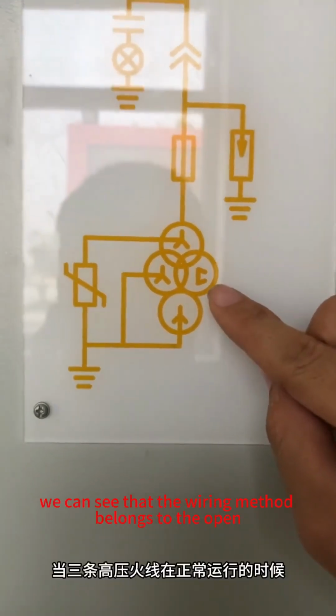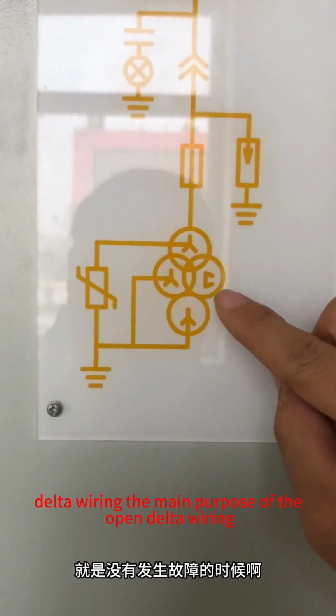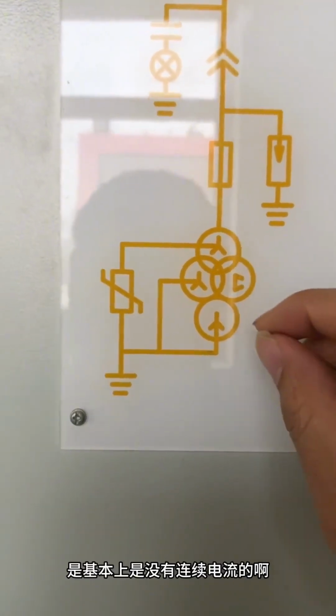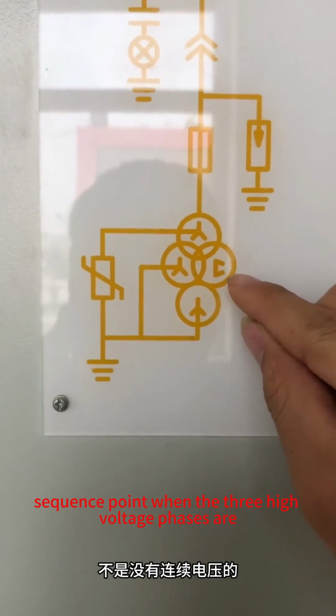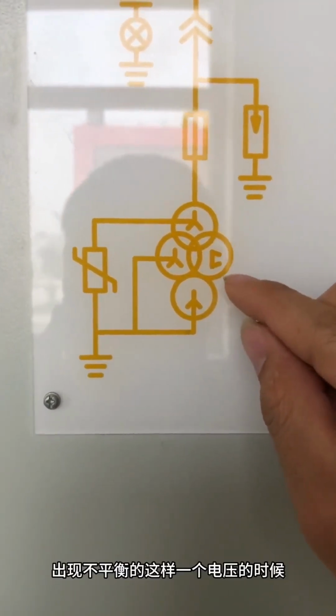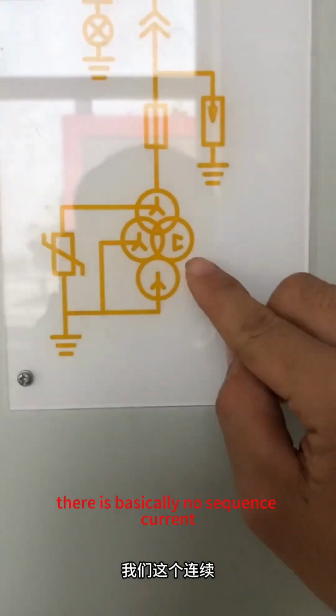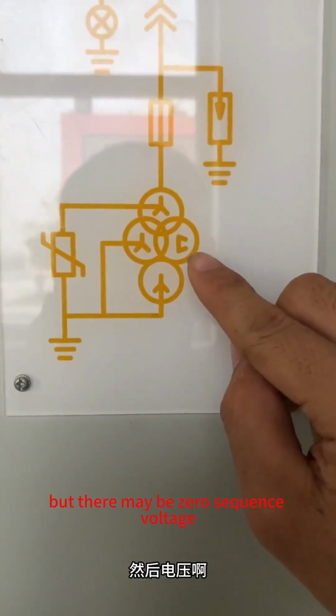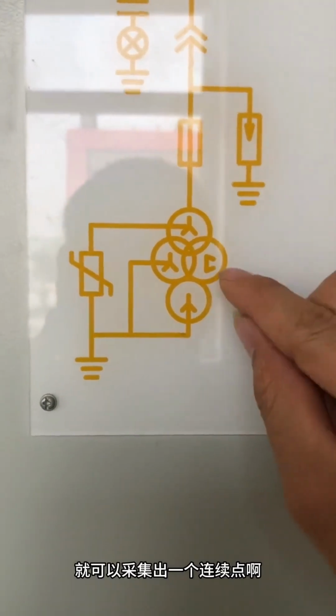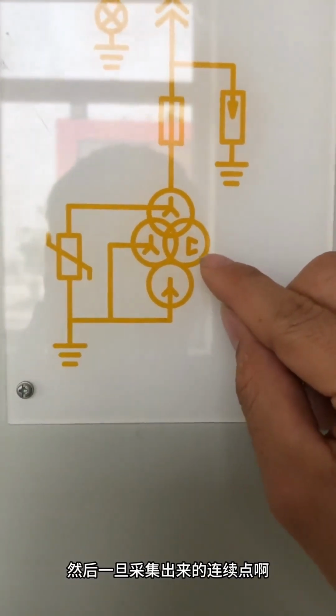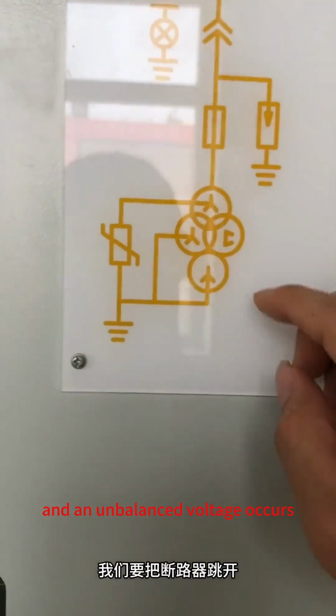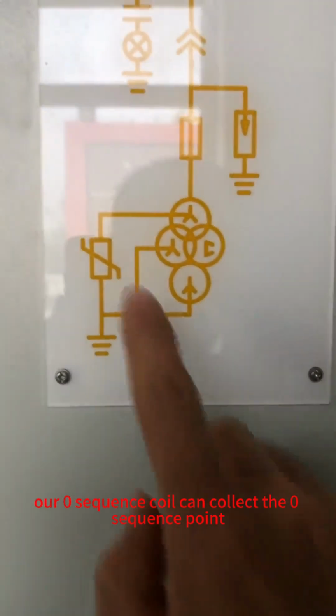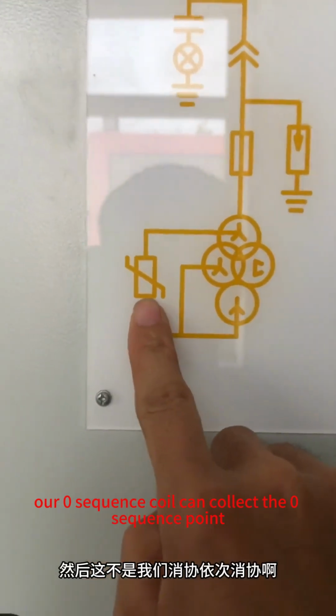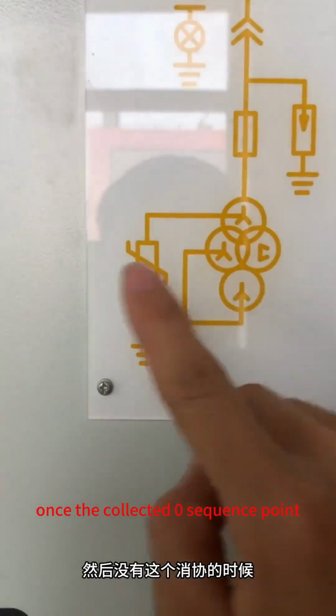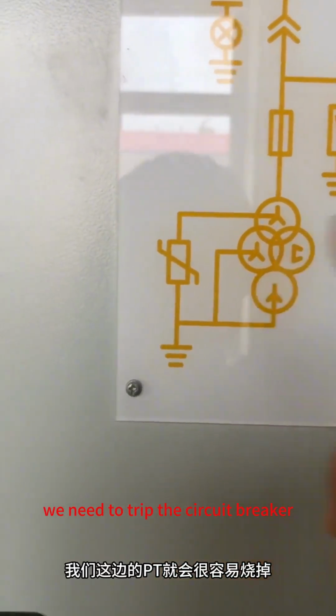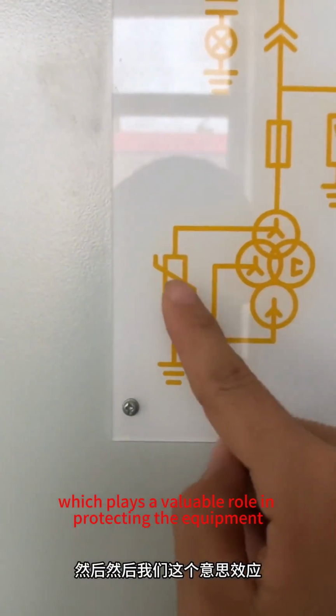Okay, we can see that this wiring method is the open delta wiring. The main purpose of the open delta wiring is to collect the zero sequence voltage. When the 3 high voltage phases are operating normally, that is, when there is no fault, there is basically no zero sequence current, but there may be some zero sequence voltage. Once there is a single phase ground fault and an unbalanced voltage occurs, our zero sequence coil can collect the zero sequence voltage. Once the collected zero sequence voltage exceeds the safety value, we need to trip the circuit breaker, which plays a valuable role in protecting the equipment.